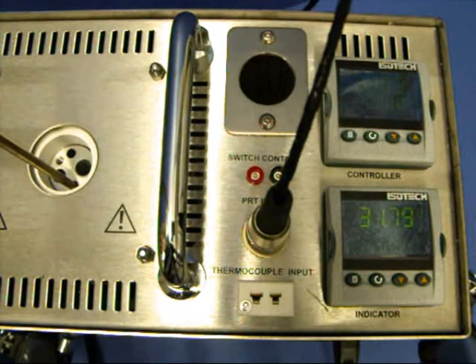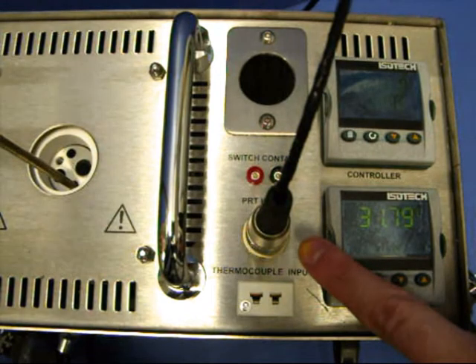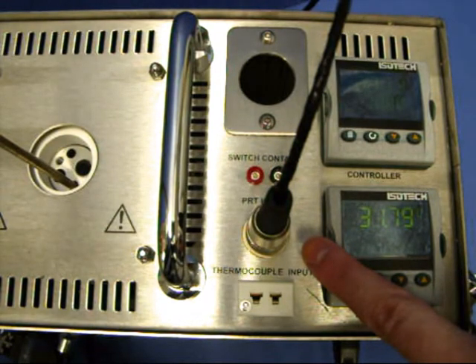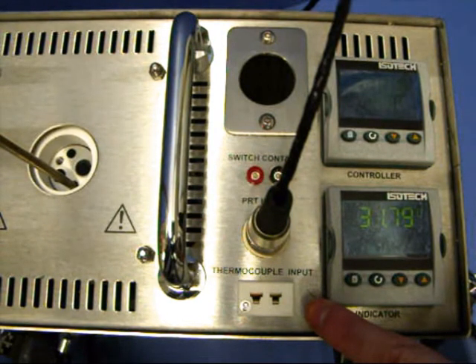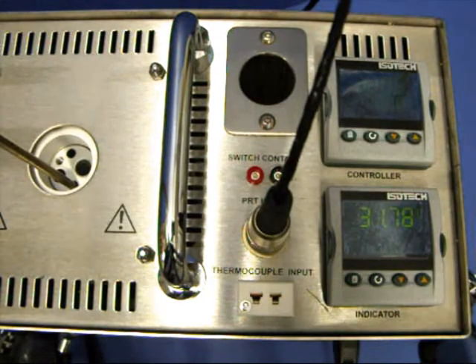Setting the input type. A 100 ohm resistance thermometer can be connected to the PRT connector or a thermocouple may be connected to the miniature thermocouple connector. Ensure that only a PRT or thermocouple are connected at any one time.